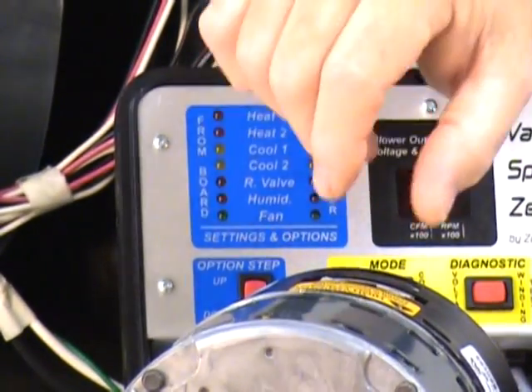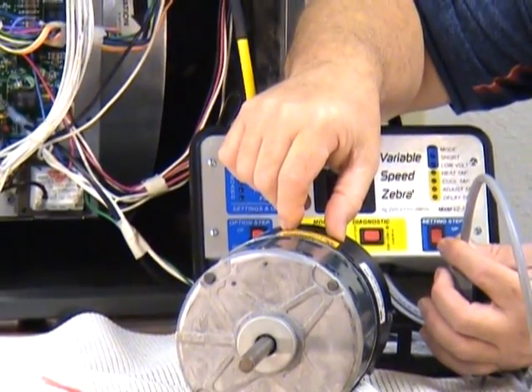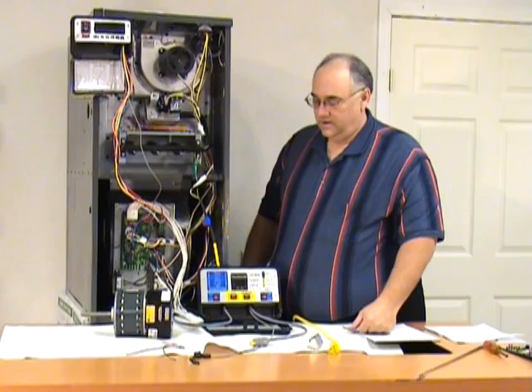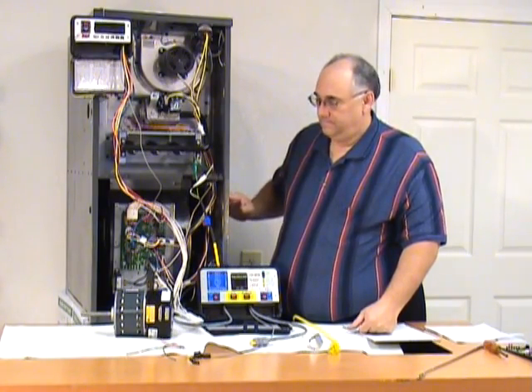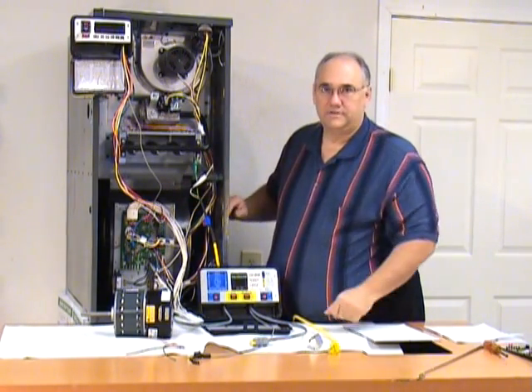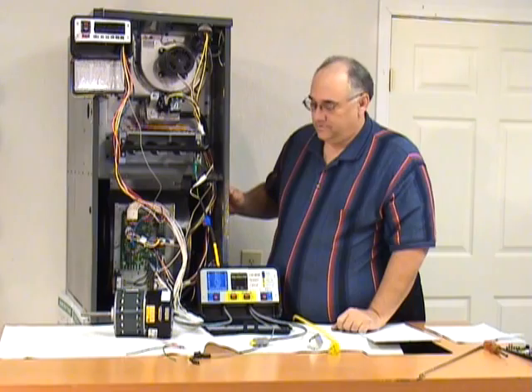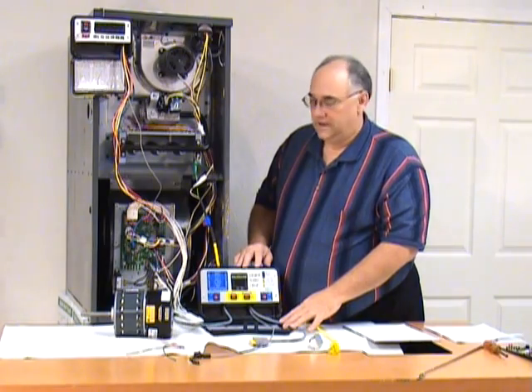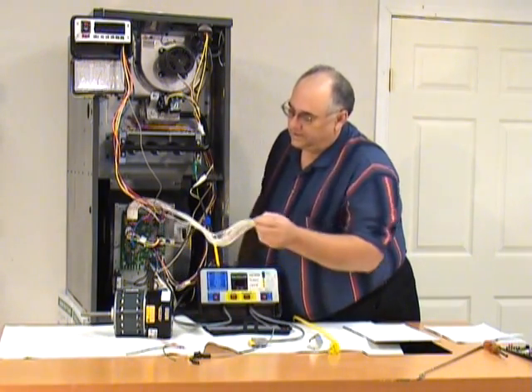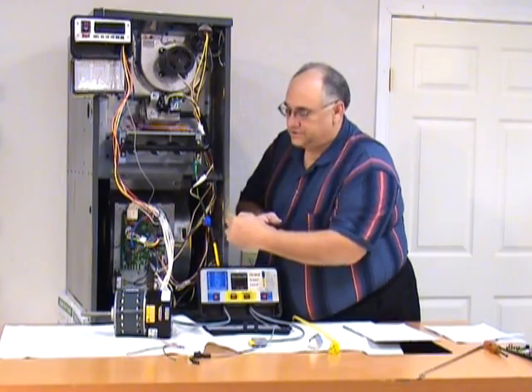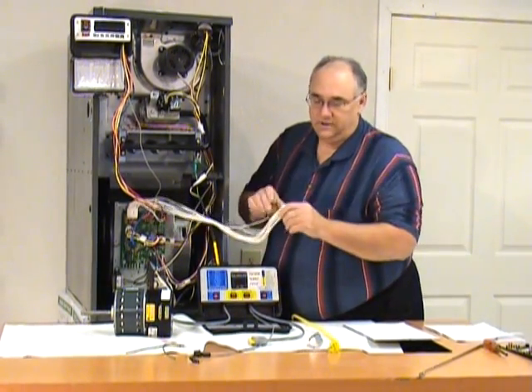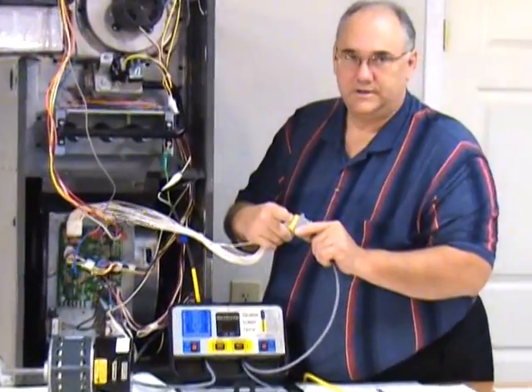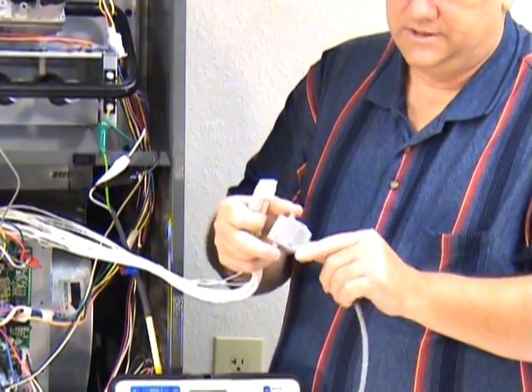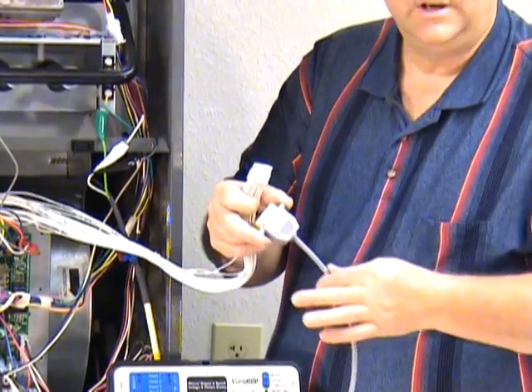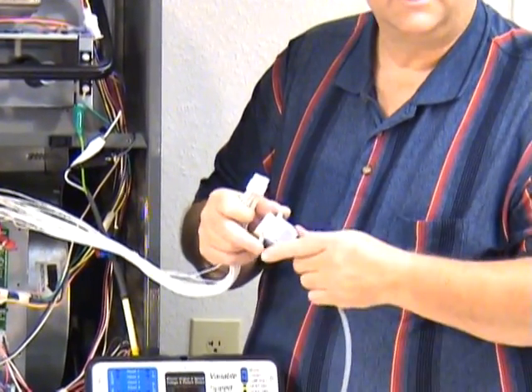to this tab on the connector to the motor, which you have to squeeze in while you're pulling out. It's pretty hard to get to that tab while the 110 or the 240 power harness is hooked up to it. After you've disconnected the power, open the door, whatever shuts the power off to your air handler or furnace, you're ready to hook up the Variable Speed Zebra in line to that motor. So you take the 16-pin connecting wire that goes from the circuit board that used to plug into the motor, and you're going to plug it into the yellow harness on the Variable Speed Zebra. A few models of the Variable Speed Zebra have harnesses that are actually yellow here. Same thing. The other wire is blue there instead.